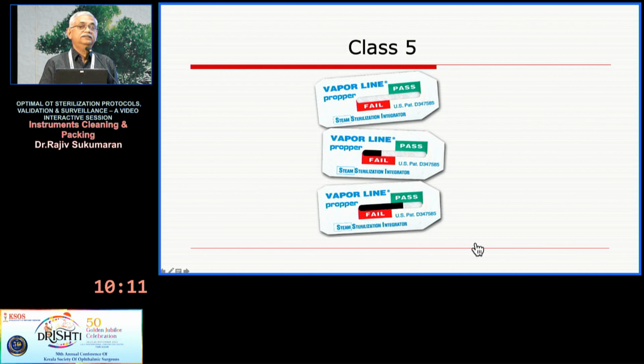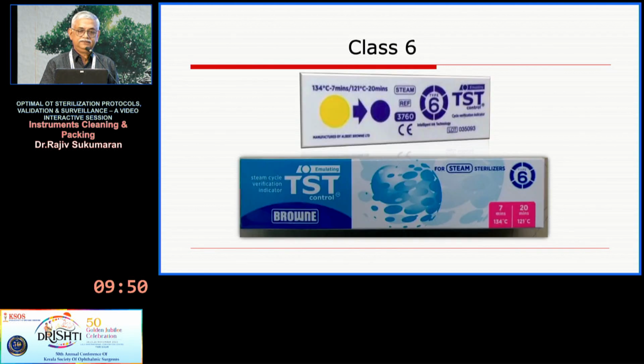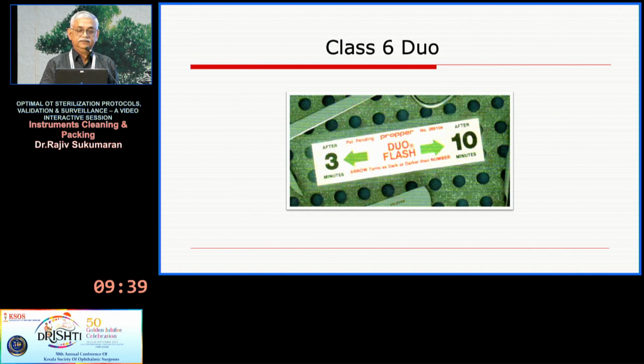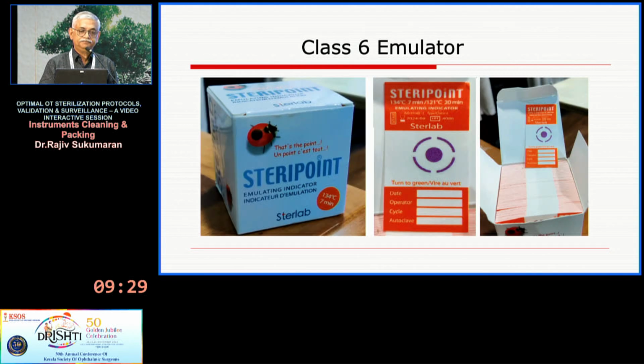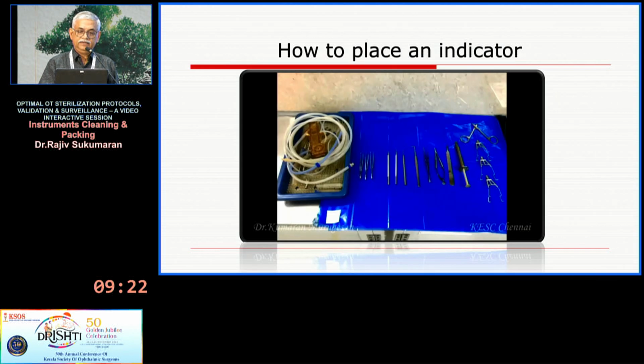Okay. And this is class 5. The disadvantage with this is, see, it says pass, fail. If the black passes in between, passes partially, we still say it is passed. But class 6 abruptly changes from yellow to blue once the autoclave process is over. So class 6 is a little better than this. It is a dual indicator, showing whether your sterilization occurred within 3 minutes or 10 minutes. So it's a dual thing. These are the different class 6 emulators available in the market, and the color change also.